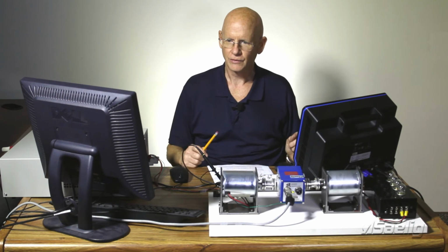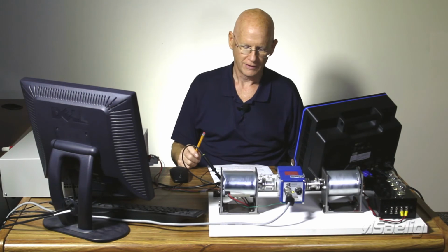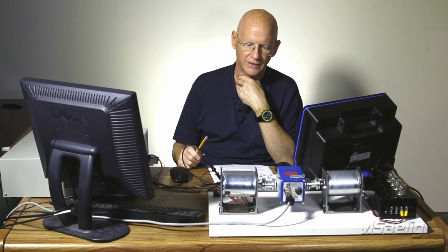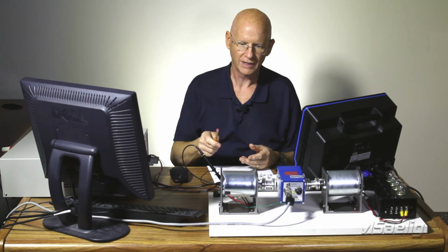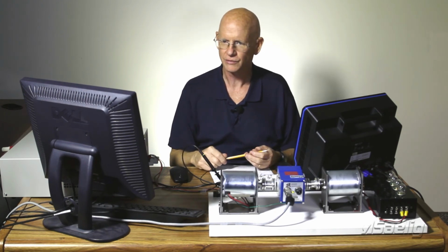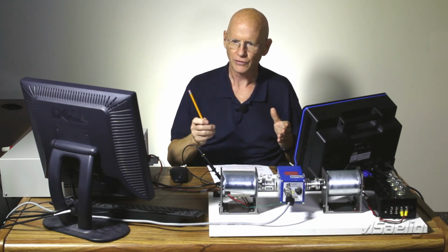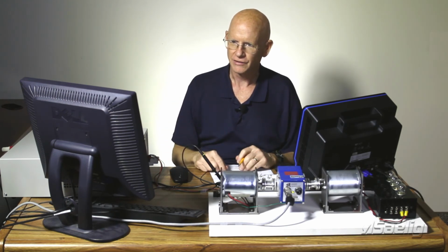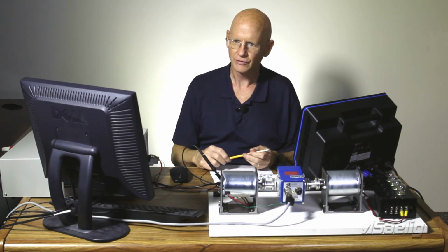And finally, we're going to use the oscilloscope and TorqView together to get a starting impulse torque and current value on the motor when we are running it at full load, at basically its half speed point. So we're going to actually start it up there and get an impulse reading for the torque and also for the current, and you'll see that in both the TorqView 5 and the oscilloscope screen. So that's what we're going to do. We're going to go through these things in detail in the next video.